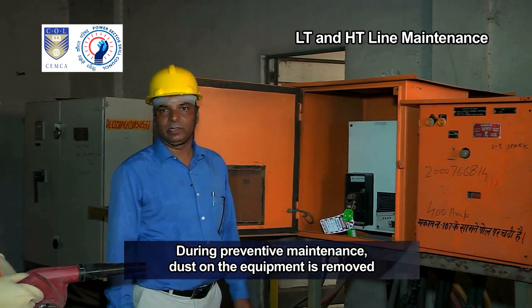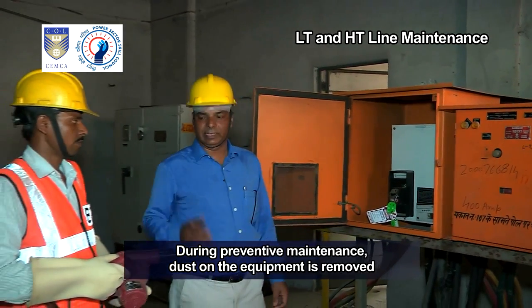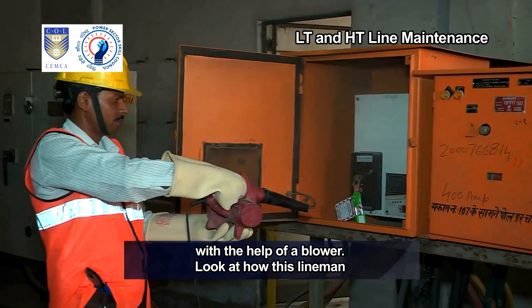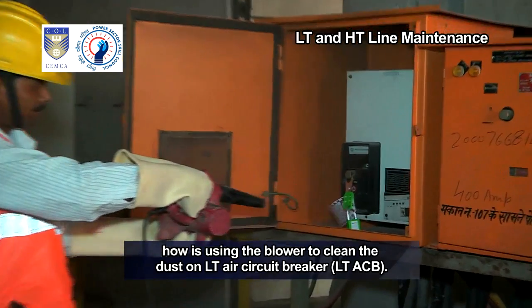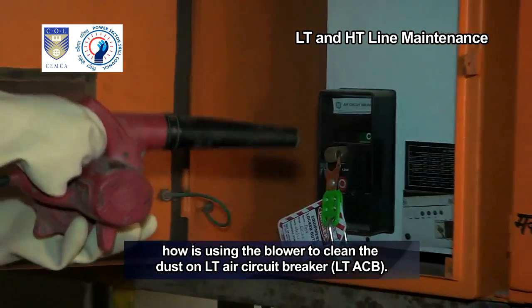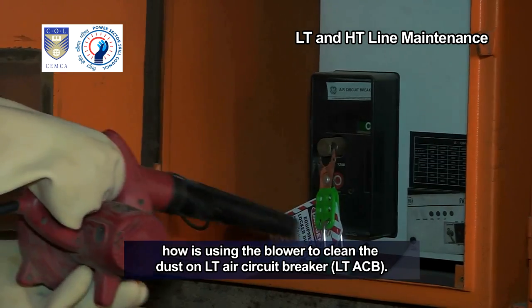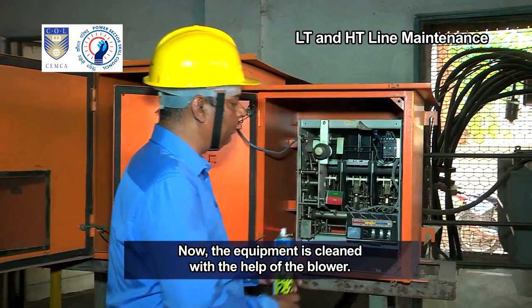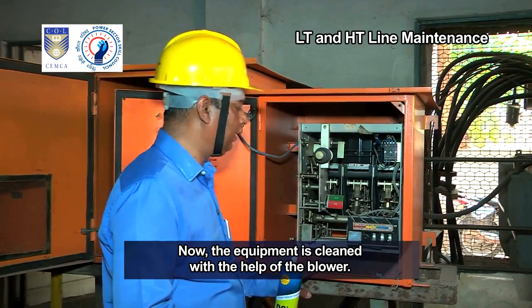During preventive maintenance, dust on the equipment is removed with the help of a blower. Look at how this lineman is using the blower to clean the dust on LT air circuit breaker, LTACB. Now the equipment is cleaned with the help of the blower.